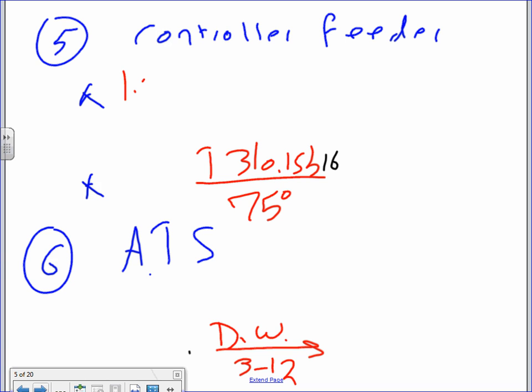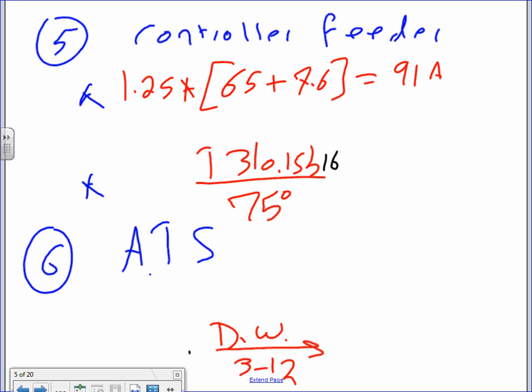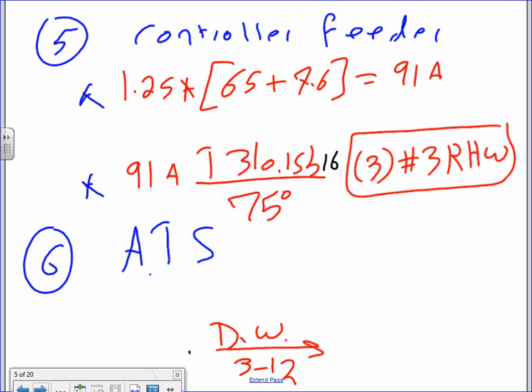We take 1.25 multiplied by both full load current, right? There you go, 65 plus 7.6. You add them up and then you multiply. It'll give you 91 amps. And then you take your 91 amps to Table 310.15(B)(16), 75-degree column. That will get you 3 conductors, number 3 RHW. Does that make sense? Does it make sense, guys? That's your conductor.